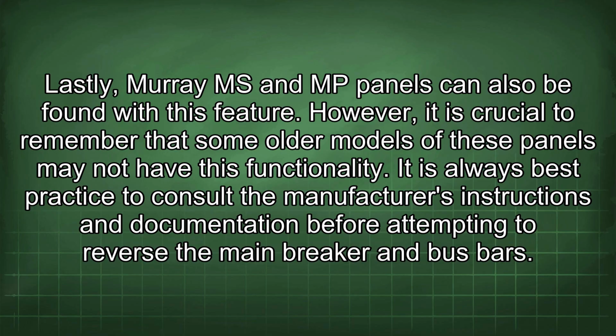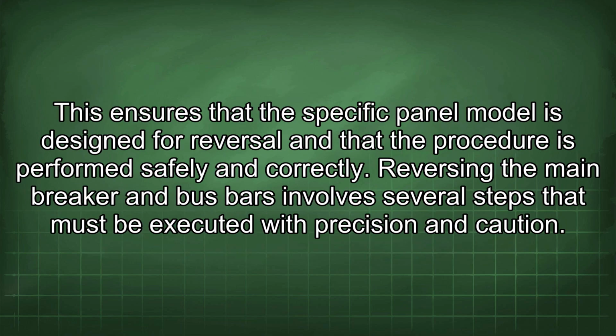However, it is crucial to remember that some older models of these panels may not have this functionality. It is always best practice to consult the manufacturer's instructions and documentation before attempting to reverse the main breaker and bus bars. This ensures that the specific panel model is designed for reversal and that the procedure is performed safely and correctly. Reversing the main breaker and bus bars involves several steps that must be executed with precision and caution.